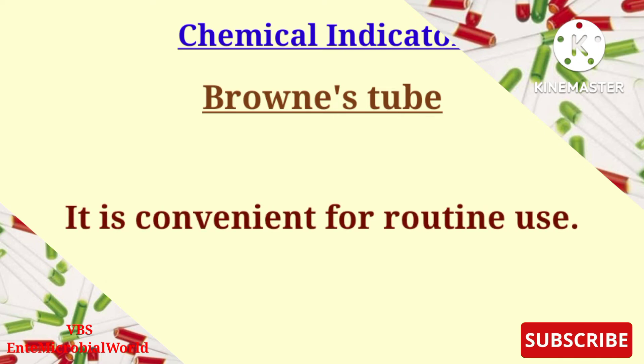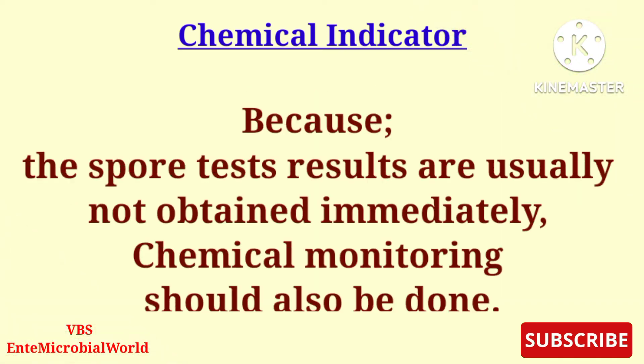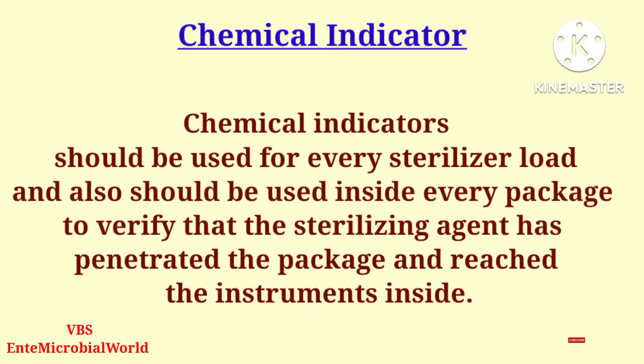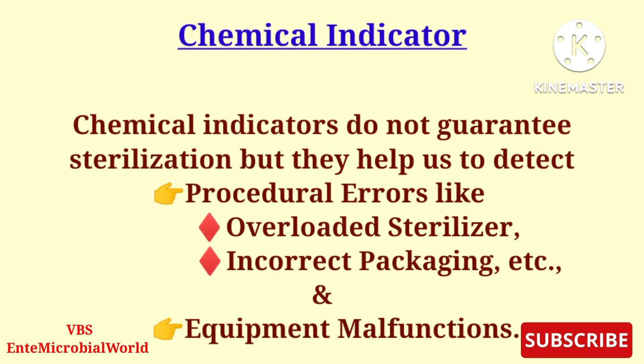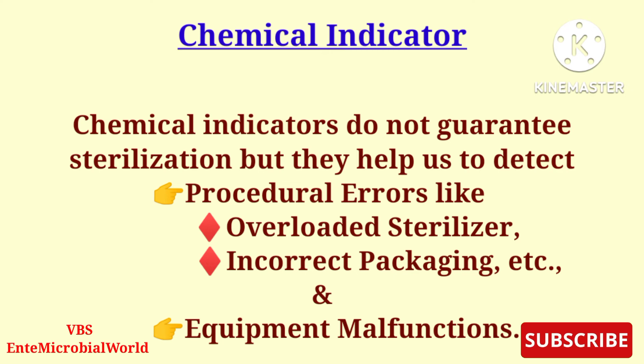Browne's tube is convenient for routine use. Because spore test results are not obtained immediately, chemical monitoring should also be done. Chemical indicators should be used for every sterilizer load and inside every package to verify that the sterilizing agent has penetrated the package and reached the instruments inside. Chemical indicators do not guarantee sterilization, but they help detect procedural errors like overloaded sterilizers, incorrect packaging, and equipment malfunctions.